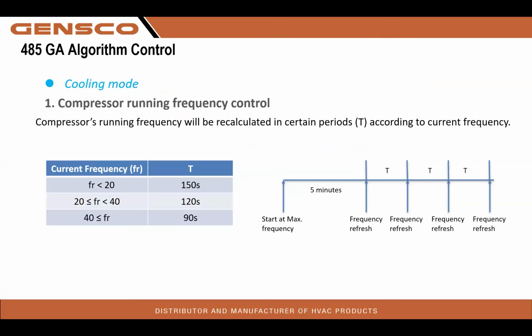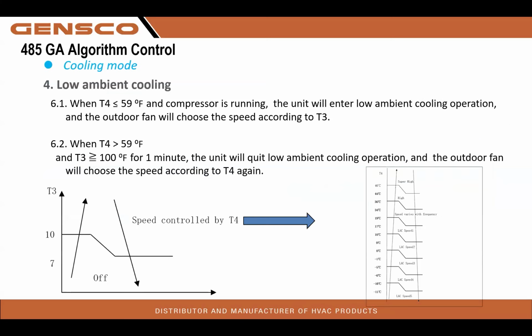Cooling mode, compressor run frequency will be recalculated in certain periods of time according to current frequency. So basically, this thing is going to run and make adjustments as needed based on time and temperature. Low ambient cooling, when T4 is below 59 degrees and the compressor is running, the unit will enter low ambient cooling operation and the outdoor fan will choose what speed it wants to run at to build head pressure for low ambient cooling, which in this application with this equipment, we can choose to turn that heat pump into a straight AC, like discussed.